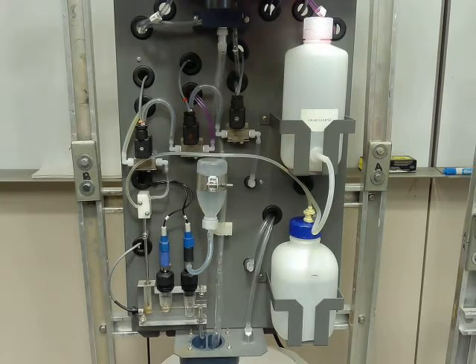And again, fill that bottle about 3/4, 7/8 of the way full. You do want to leave a little bit of space at the top of the bottle, because we're using the vapor, and you want to make sure that vapor has a place to build up its vapor pressure so that it drains into the sample properly.